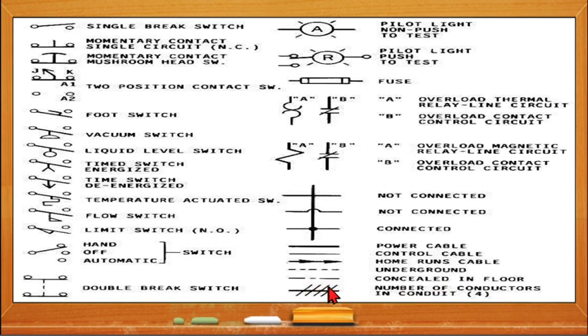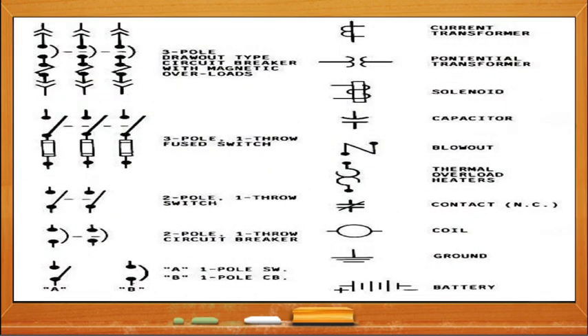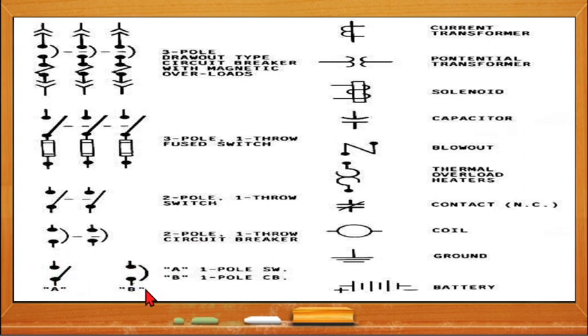We also have concealed-in-floor wiring. The piping symbol indicates how many conductors are present — the number of tick marks on the line shows the conductor count; four lines means four conductors in that pipe. For protection, we have symbols for a three-pole breaker with magnetic overloads, the single-throw three-pole fuse switch or main safety switch, the two-pole single-throw breaker, a single pole switch, and a single pole breaker. Additional symbols include the current transformer, potential transformer, solenoid, capacitor, blowout, thermal overload heaters, normally closed contact, normally open contact, coil, ground, and battery.